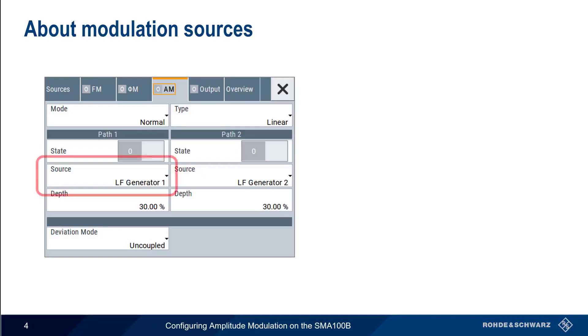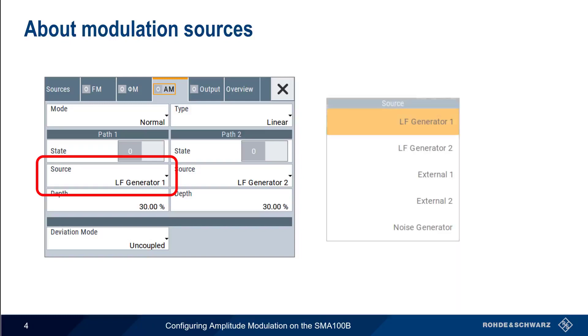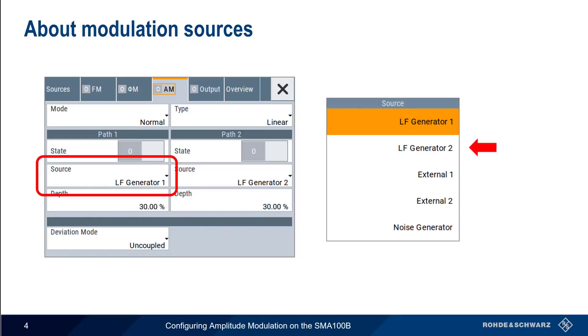A number of different modulation sources can be used with the SMA100B. Some of these sources are internal to the instrument, and others are external. Internal sources of modulation include the two low-frequency, or LF, generators, as well as the noise generator. We'll start by looking at internal AM modulation sources.